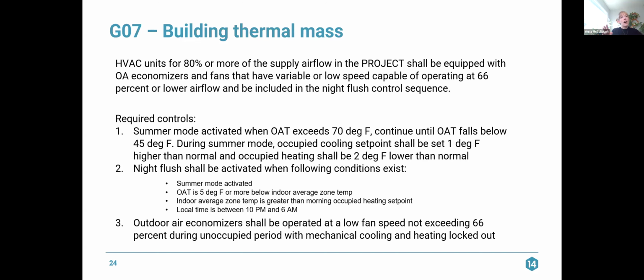If you are not in summer mode, you are not doing a night flush. So if it is winter, it is cold outside, we are not freezing the building. It's only when we have cool nighttime air available. And that's the idea, right, in the winter, we want that thermal mass to release warm air into the occupied space. And in the summer, we want to use the cool nighttime air when that is available to cool down the occupied space. It was a lot.